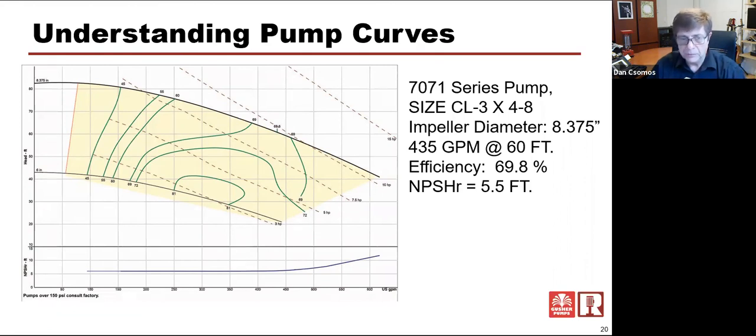You know, a lot of things could go on. If you're underperforming, it may be air entrainment or cavitation or something too. All of this stuff kind of correlates to each other to be able to tell you information, at least give you a very educated guess, if that makes sense.